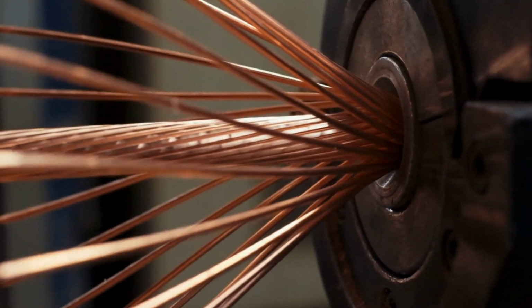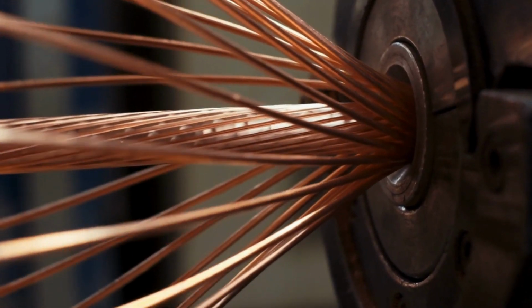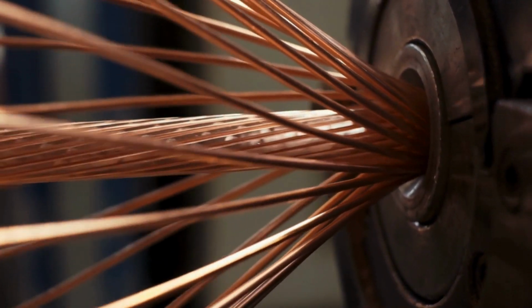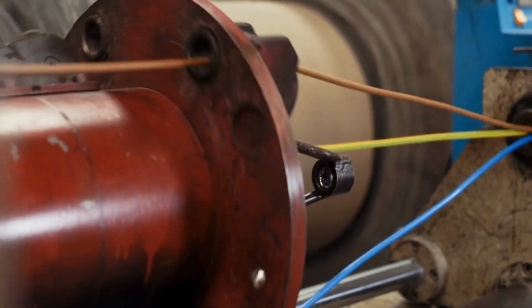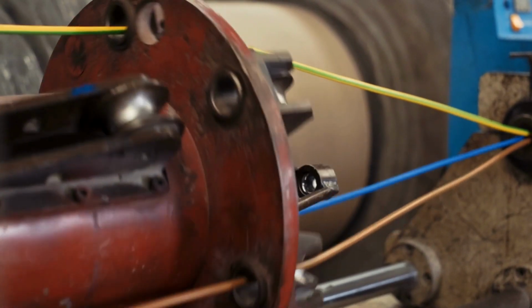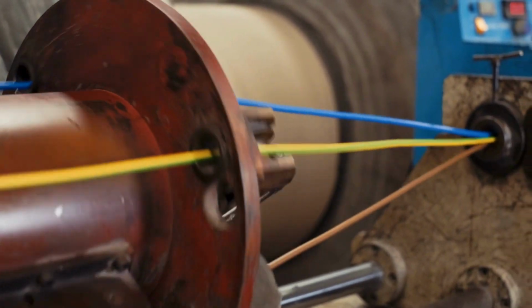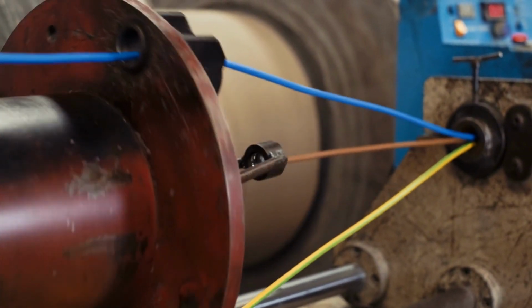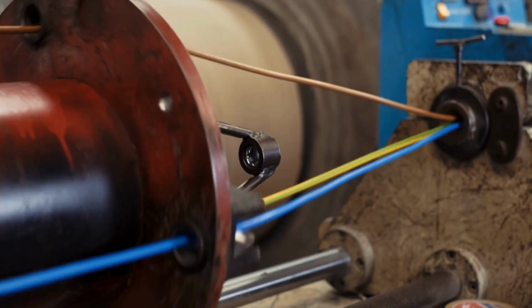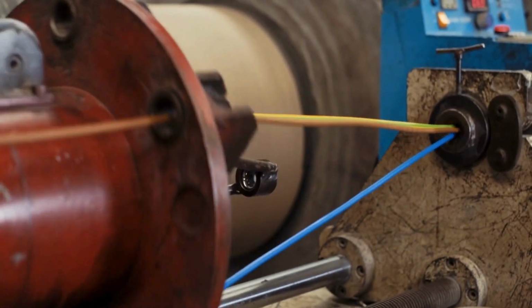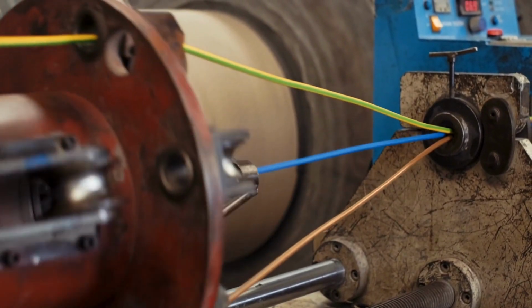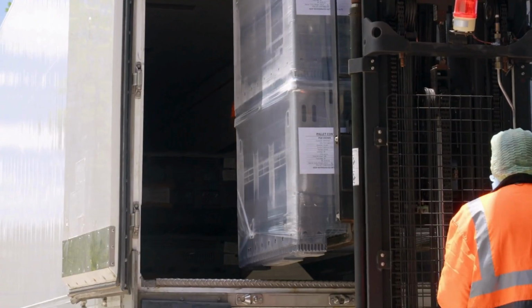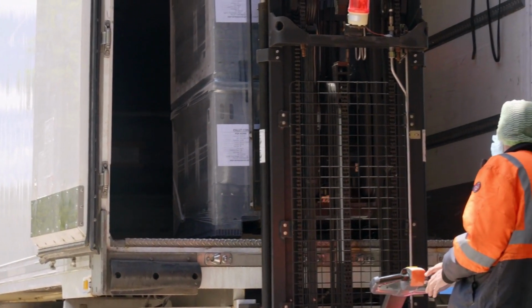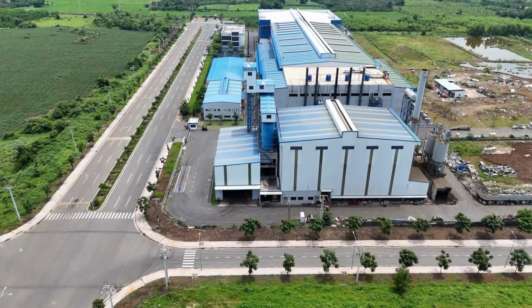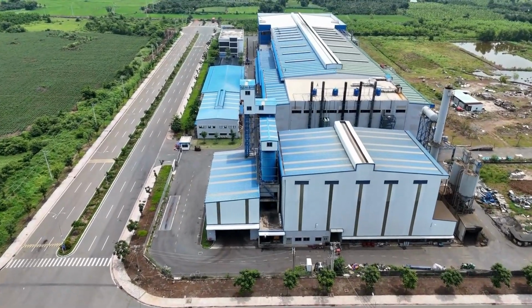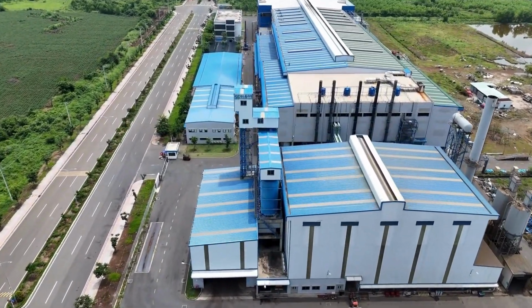Offline quality control tests are equally important. Electrical resistance is measured over a standardized length of wire. Resistance values provide insight into copper purity, actual conductor cross-section, and the overall stability of the drawing and stranding processes. Another critical safety test is the high potential, or high-pot, test. In this test, a voltage significantly higher than the wire's normal operating level is applied to the insulation. The goal is to verify that the insulation can withstand extreme electrical stress without breakdown or leakage.